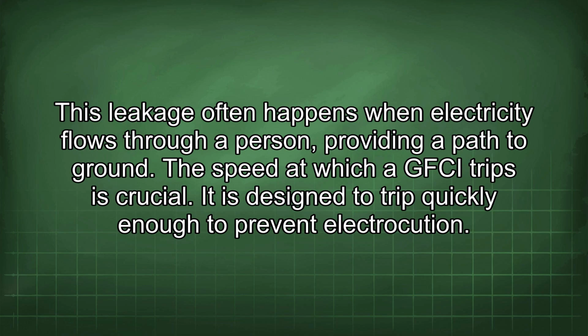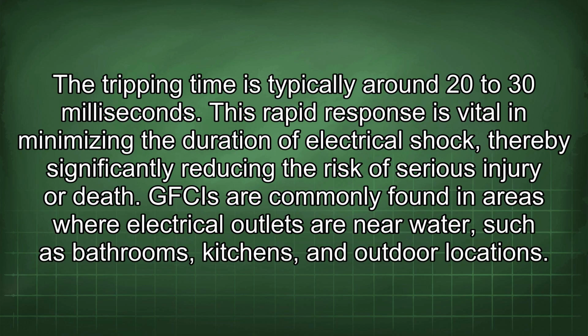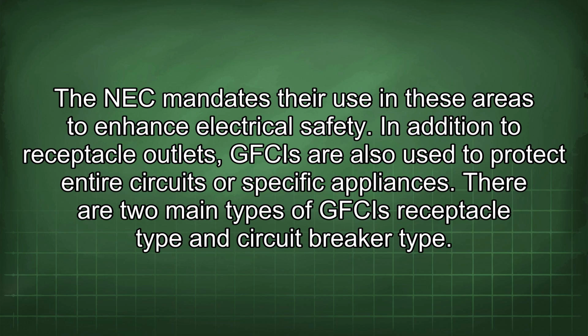The speed at which a GFCI trips is crucial. It is designed to trip quickly enough to prevent electrocution. The tripping time is typically around 20 to 30 milliseconds. This rapid response is vital in minimizing the duration of electrical shock, thereby significantly reducing the risk of serious injury or death. GFCIs are commonly found in areas where electrical outlets are near water, such as bathrooms, kitchens, and outdoor locations. The NEC mandates their use in these areas to enhance electrical safety.